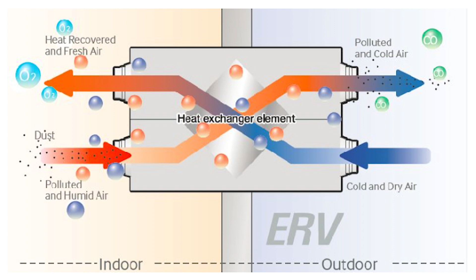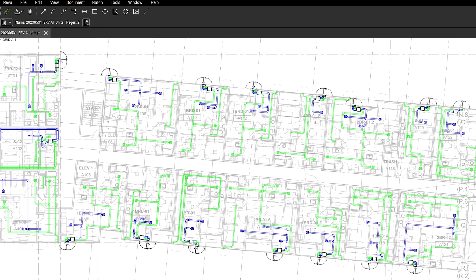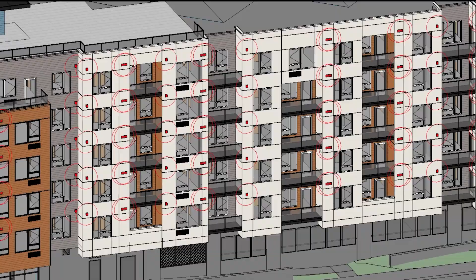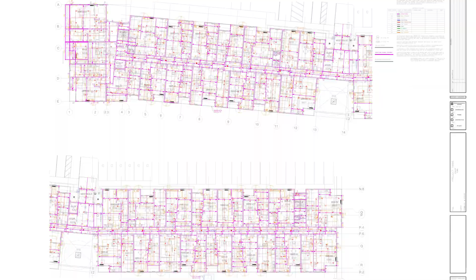The inclusion of ERVs in multifamily projects introduces a new level of pre-construction coordination, requiring seamless collaboration among key stakeholders to minimize schedule and cost disruptions. ERVs are located inside every residential unit in the building, thus requiring routing coordination of ductwork with exterior envelope penetrations and other disciplines' work, such as structural and mechanical consultants. Coordination with the structural engineer is required to ensure ducts can be routed to the building exterior without conflicting with shear walls for lateral bracing or other items required by the engineer to support the building.